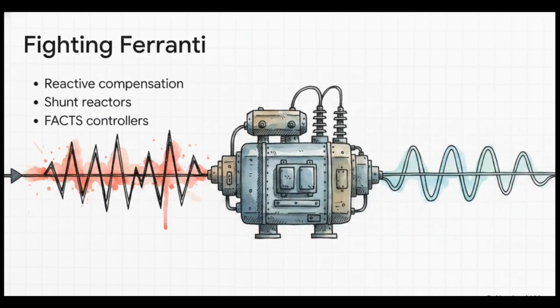Now, fighting the Ferranti effect? We don't use geometry for that. We fight it dynamically. System operators use reactive power compensation to tame that runaway excess voltage. Typically, they'll install these massive shunt reactors right at the receiving end of the line to literally absorb the excess leading reactive power. Plus, they use FACTS controllers, flexible AC transmission systems, like SVCs and STATCOMs. These are highly effective automated systems. They dynamically manage reactive power and stabilize the voltage profile the very moment those transient load changes happen. They basically keep the swing from going too high.